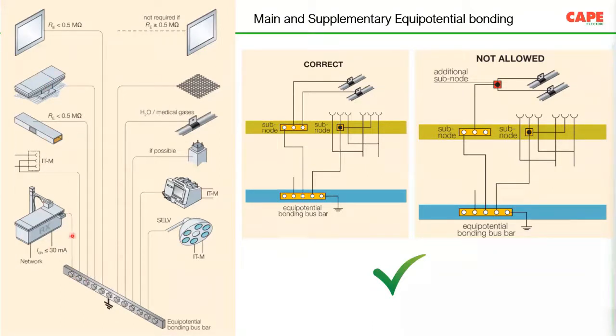For example, after making the supplementary equipotential bonding, take this particular medical gas pipe and the bus bar: the resistance between the medical pipe and the earth bus bar must be less than 0.2 ohm. So measurements are required, joint measurements are required. The rules for supplementary equipotential bonding are mandatory for medical locations, group 1 and group 2 medical locations. Please don't follow the medical equipment vendors' claim for having separate earth electrodes.